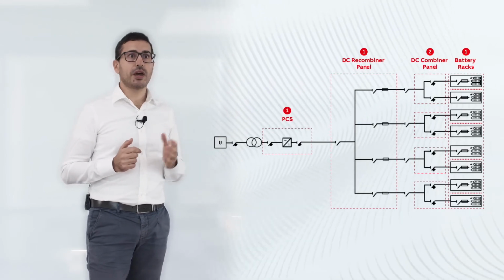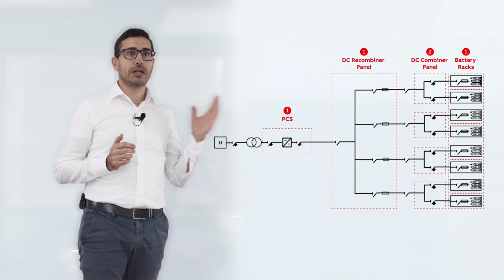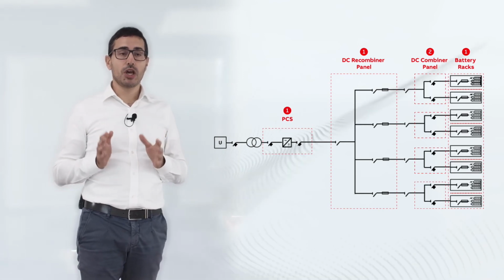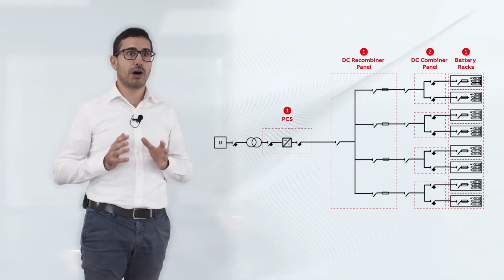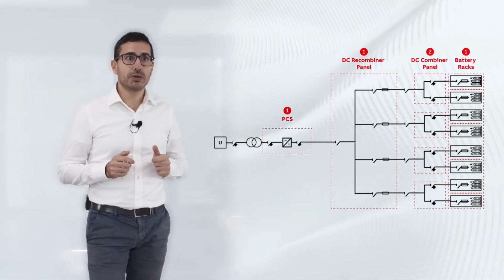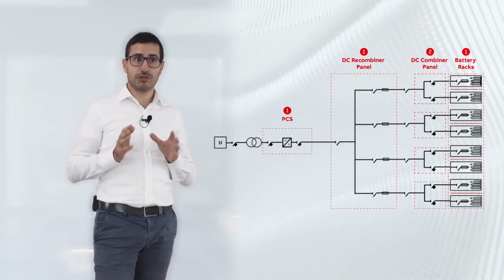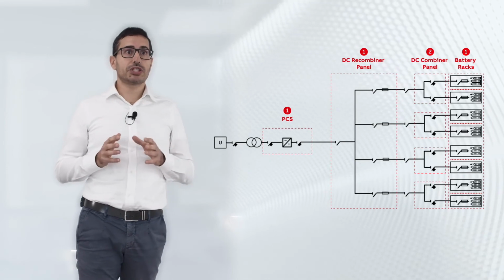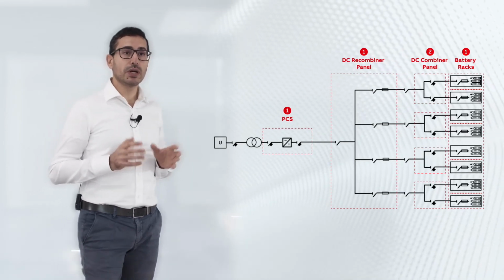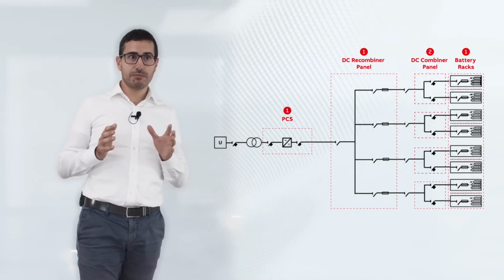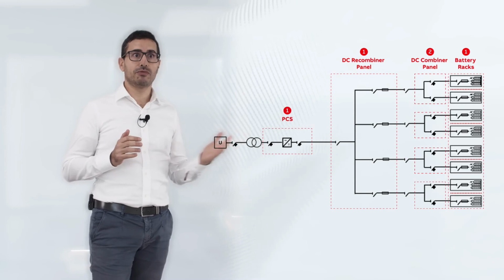So, as you can see, here we have a real example. From right to left, you may see the battery racks, which are then coupled into a DC combiner panel. Then we do encounter a recombiner DC panel. Then power is converted from DC to AC through a PCS, power conversion system, which is then converting power to the medium voltage utility. What we see here is a typical example of a 4 megawatt installation. In terms of energy, this may easily reach 2 megawatt hours of energy.